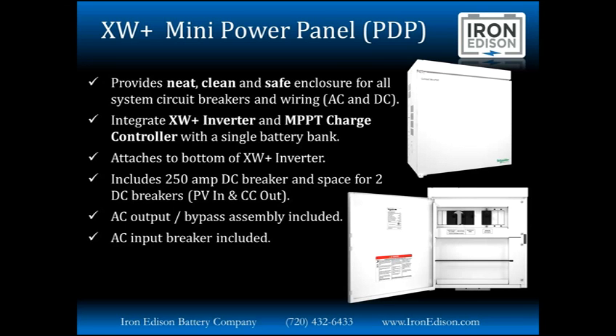As I said before, the power distribution panel is such a critical part of a great looking and code compliant installation. If it's really a huge struggle to try to mount these 250 amp DC disconnects and the AC input output bypass assembly, the DC circuit breakers for the charge controllers elsewhere, that's not a good idea. We highly recommend using these power panels.